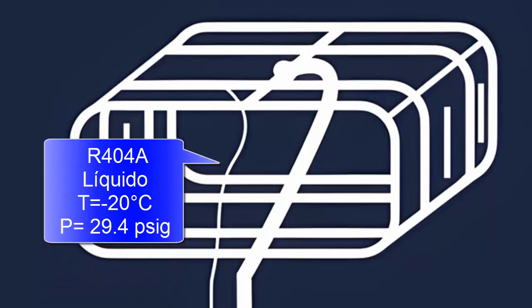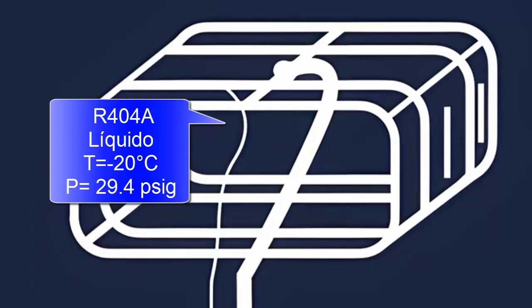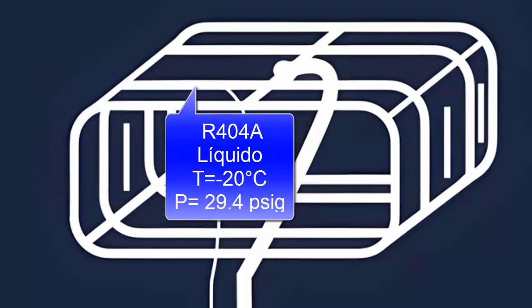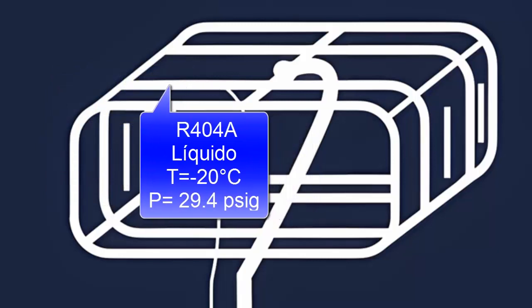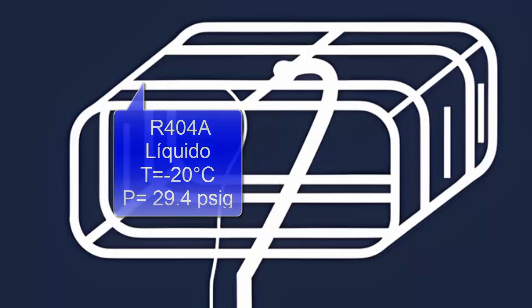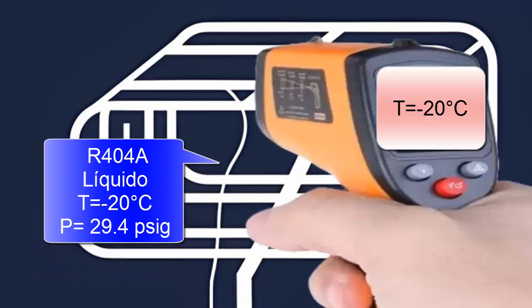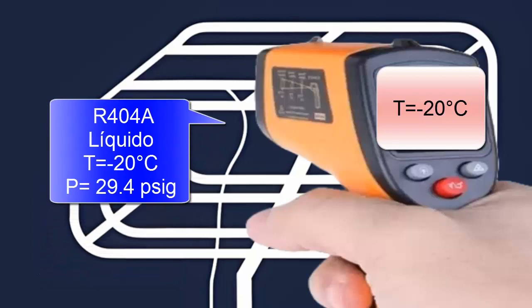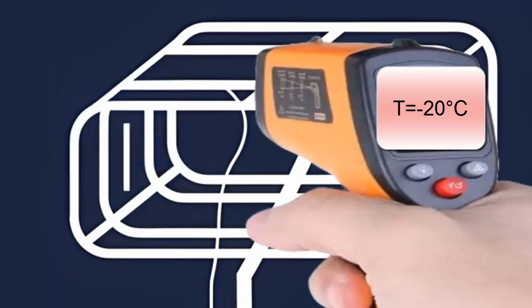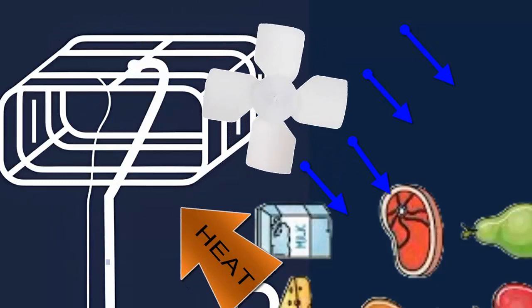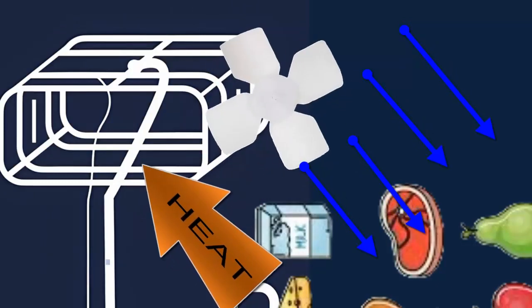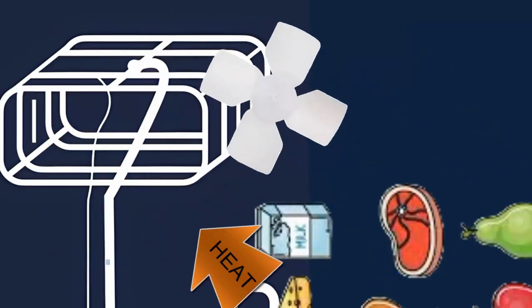The R404A refrigerant enters the evaporator in a liquid state, at a pressure of 29.4 pounds per square inch. With this pressure, it is achieved that the R404A in the evaporator has a temperature of minus 20 degrees Celsius. With this low temperature and the help of the fan, the heat from the food quickly passes to the refrigerant R404A, causing it to evaporate.